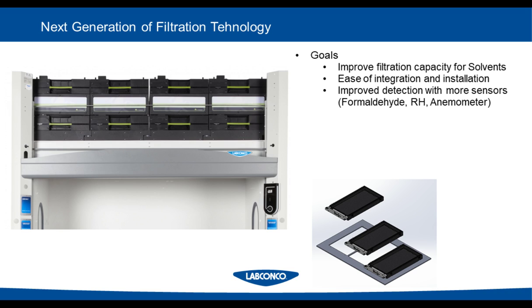Also a relative humidity sensor in each fan module. And the temperature sensor was already there, but we've now moved it up into each fan module also. And then lastly, adding an anemometer, so we'll measure directly the face velocity - that's the speed at which air is moving into the fume hood. It's a very good indicator of safety, though containment testing is the final indicator of that.